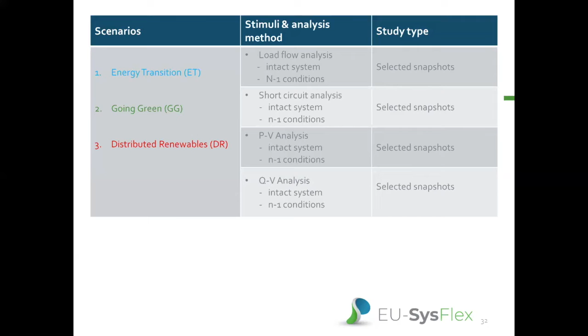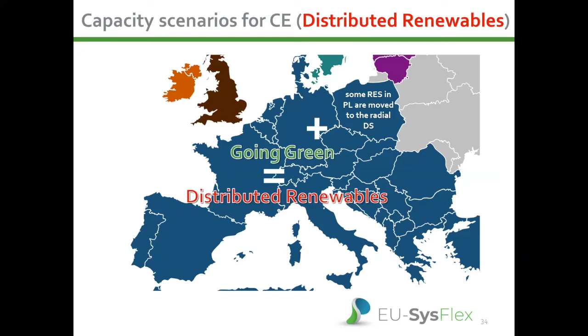Steady state voltage control has been analyzed for 3 capacity scenarios, which have been considered both in the voltage and transient stability studies for the Central Europe power system model. The first scenario is the core EU-SysFlex energy transition. Going green assumes more installed renewable capacity in Poland, mainly connected to the extra high and high voltage grid. Another scenario, distributed renewables, assumes that some renewables in Poland are moved to the radial distribution systems.